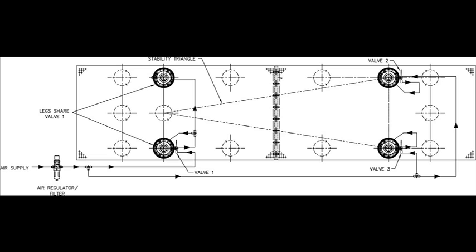In this first example, an end-to-end doubler system is shown being supported by four S2000 isolators, which have a 2,000-pound load capacity for each isolator. The lab air supply line is connected to an air regulating filter (ARF) that regulates the air into the isolation system and also helps keep the supply air clean. The output of the ARF is delivered to three leveling valves that are used to define the plane of the table.